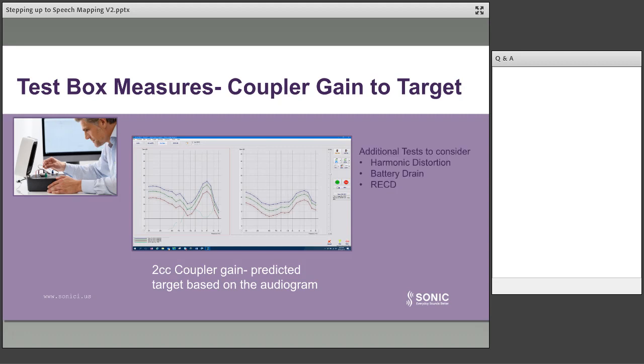There are other tests that you can do as well that are worthwhile considering. You can measure the harmonic distortion in the hearing aid. As hearing aids get older, a certain amount of distortion comes into the signal, and the client may not even notice that because they've been getting so used to it over time. You can measure the battery drain of a device if you're concerned that batteries are being used up too quickly. And you can also perform real ear to coupler difference measures so that you can have an even more precise target match for your hearing aids in the box.